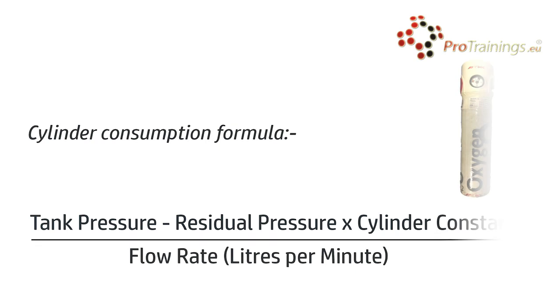The first figure you'll need to know is the cylinder pressure. This should be on the cylinder or you can ask your supplier. In the example we're using, the pressure will be 2000 psi. We'll need to take off a residual pressure of 200 psi. This will allow 200 psi for errors in calculation or initial cylinder filler errors, and also give a short extra supply.